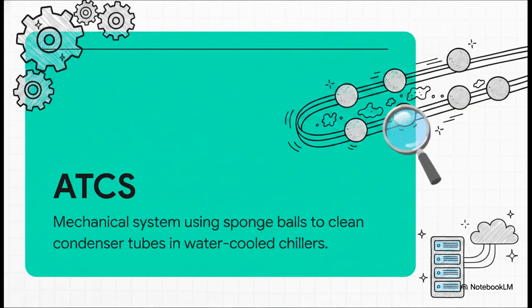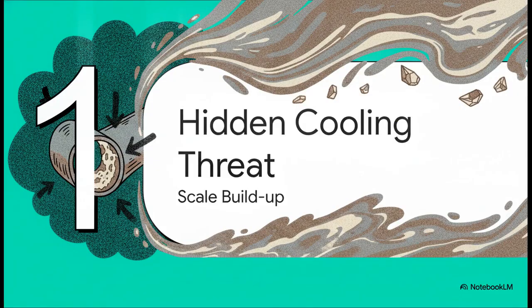And that brings us to our unsung hero, the Automatic Tube Cleaning System, or ATCS. Out in the field, a lot of folks just call it a sponge ball cleaning system, which honestly hits the nail on the head. It's exactly what it sounds like. It's a mechanical setup that uses tiny, simple sponge balls to continuously scrub the inside of condenser tubes in water-cooled chillers. It's just this tiny, simple object doing a massive, critical job, scrubbing away threats before they can take down our digital infrastructure. The hidden cooling threat.